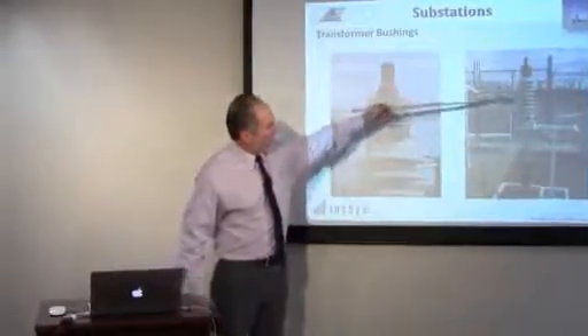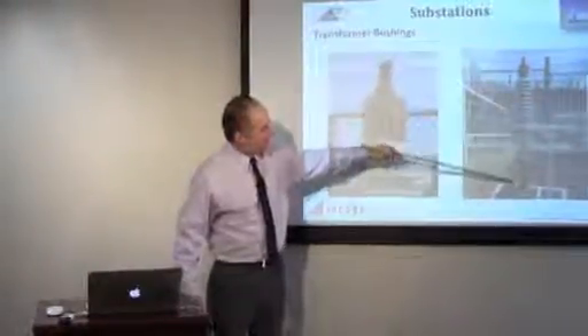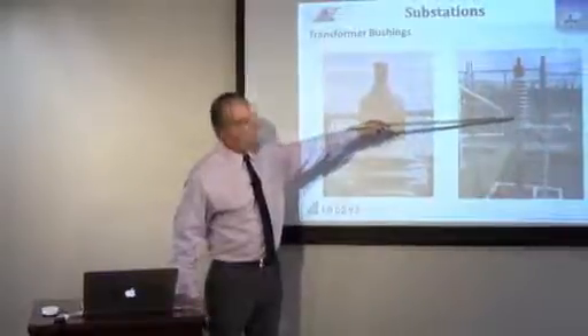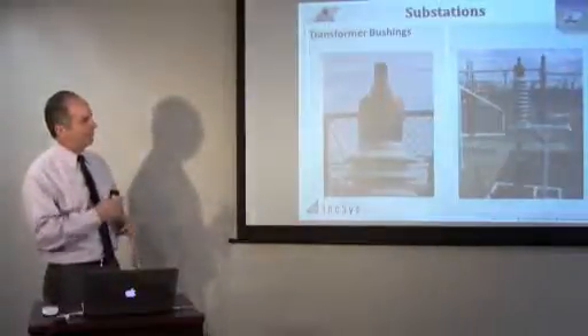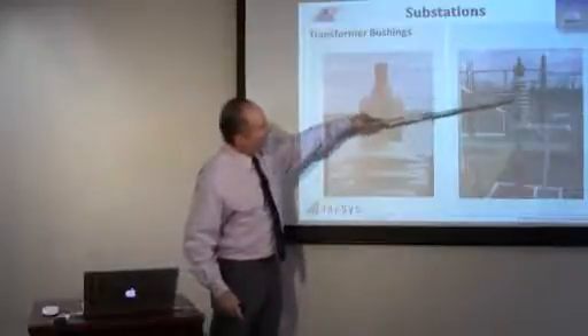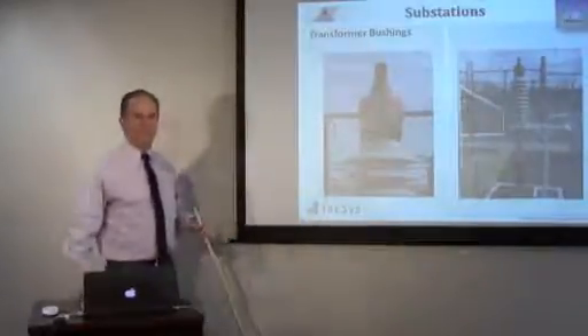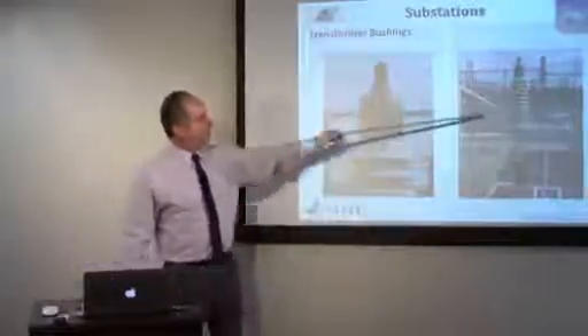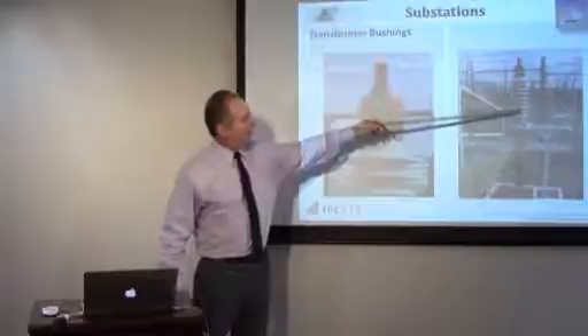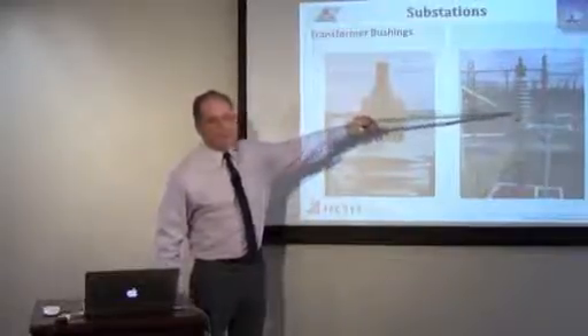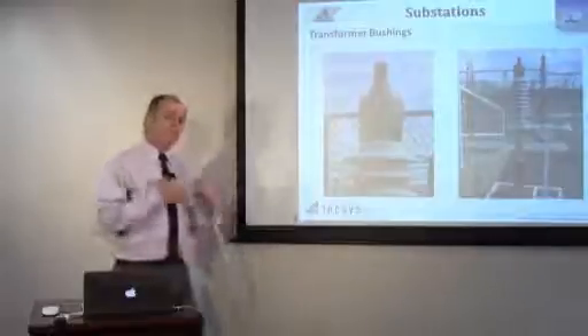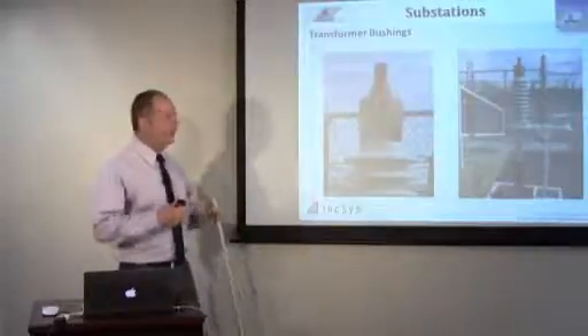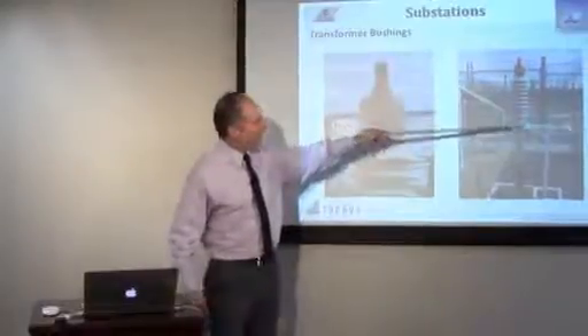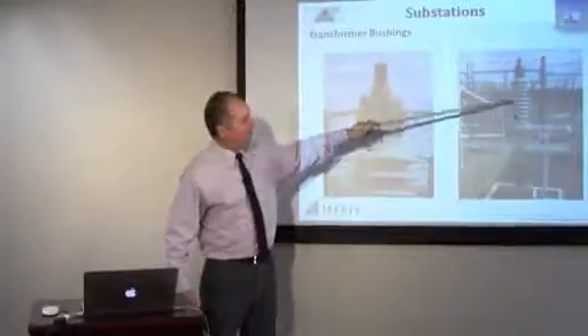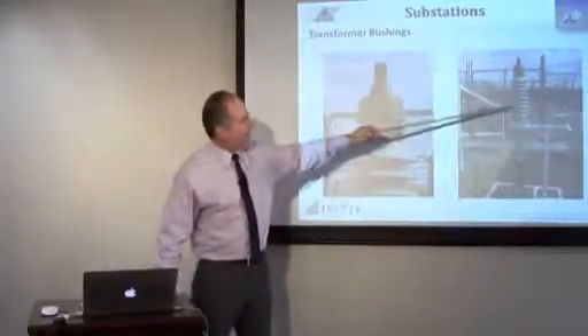Here's the full bushing. This part would be inside the transformer or circuit breaker. Notice the skirts, or the ribs, or the different terms for them on the bushing. The reason for all that is, when you're exposed to the outside environment, contaminants can collect on there, and then if you get moisture or condensation, the contaminants could be conductive, and the moisture makes a conductive path between the high voltage lead and the grounded tank. So you could have leakage currents, and if you get a lot of leakage currents, then you can get arcing underneath here, dry band arcing.